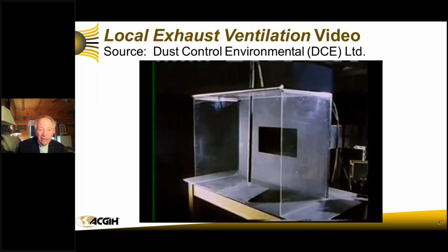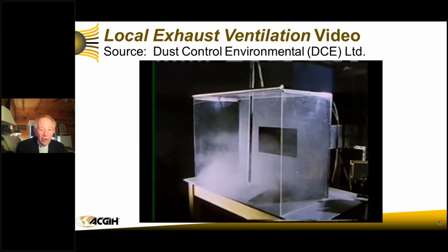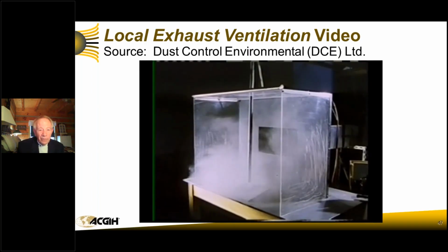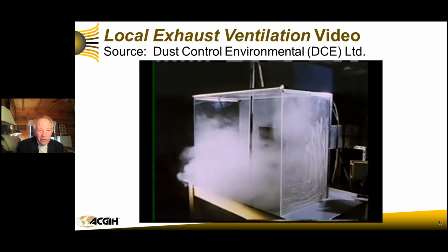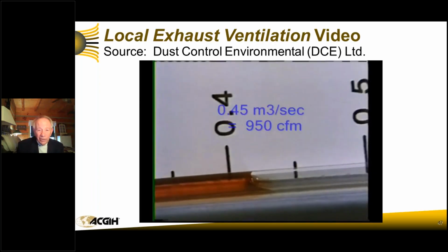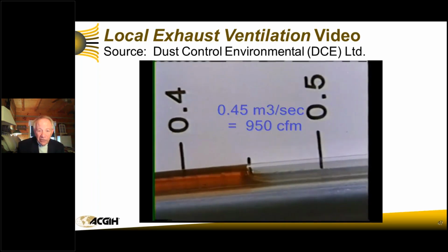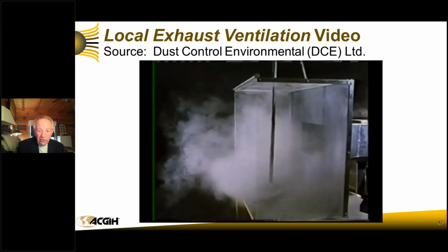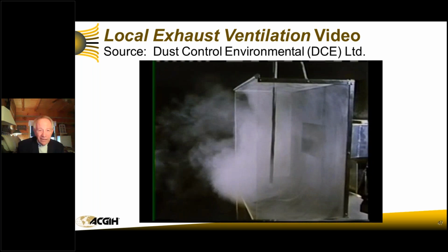Now let's remove the face and open up the face a little bit more. Well, not nearly so good. Now you're projecting. Unfortunately, we can't help it. We're projecting some limestone dust out, and now a human body, even a human body moving at 200 feet a minute, will cause some of the dust to come out and affect the employee.